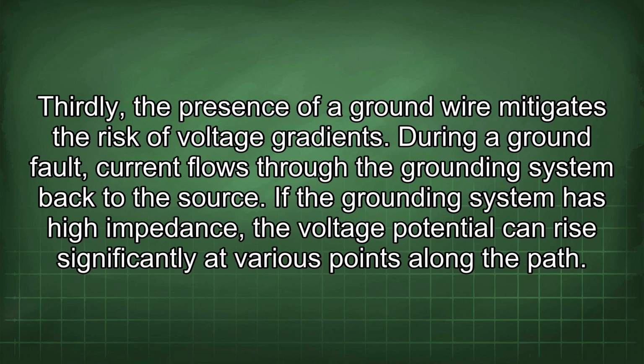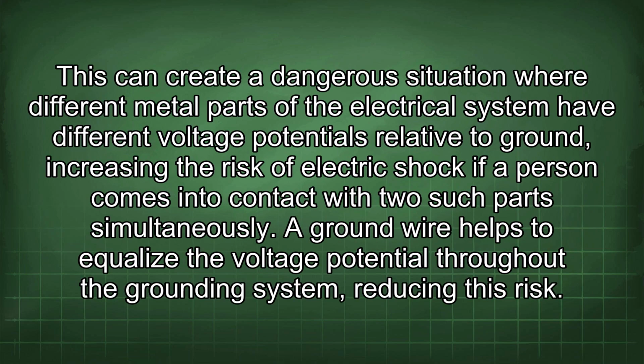Thirdly, the presence of a ground wire mitigates the risk of voltage gradients. During a ground fault, current flows through the grounding system back to the source. If the grounding system has high impedance, the voltage potential can rise significantly at various points along the path. This can create a dangerous situation where different metal parts of the electrical system have different voltage potentials relative to ground, increasing the risk of electric shock if a person comes into contact with two such parts simultaneously. A ground wire helps to equalize the voltage potential throughout the grounding system, reducing this risk.